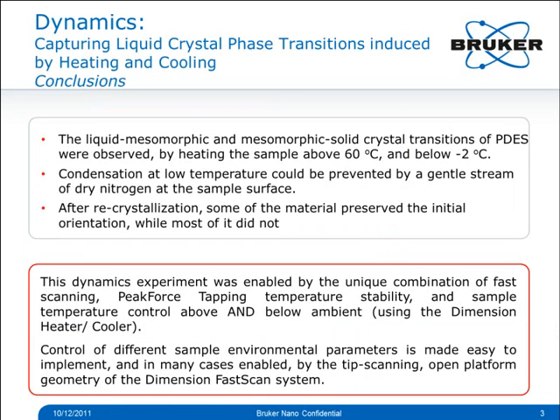Conclusions. The liquid mesomorphic and mesomorphic solid crystal transitions of PDES were observed by heating the sample above 60 degrees C and cooling below minus 2 degrees C. Condensation at low temperature could be prevented by a gentle stream of dry nitrogen directed at the sample surface. After recrystallization, some of the material preserved the initial orientation while most of it did not. This dynamics experiment was enabled by the unique combination of fast scanning, Peak Force Tapping, temperature stability, and sample temperature control above and below ambient using the Dimension Heater Cooler. Control of different sample environmental parameters is made easy to implement and in many cases enabled by the tip-scanning open platform geometry of the Dimension FastScan system.